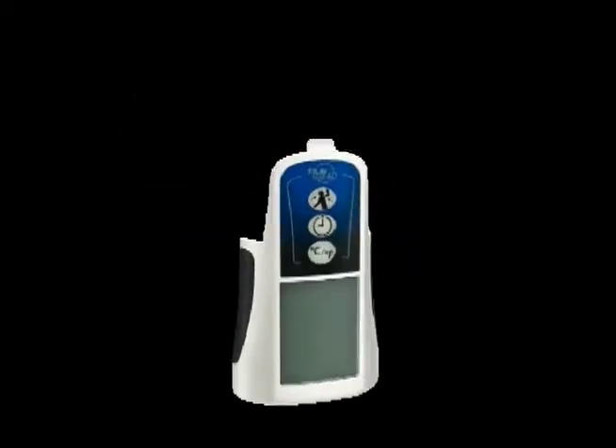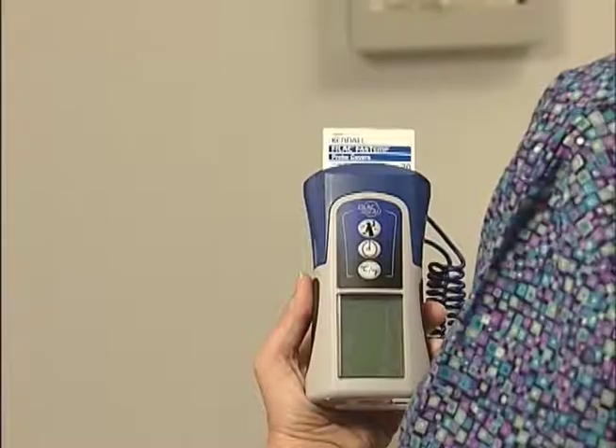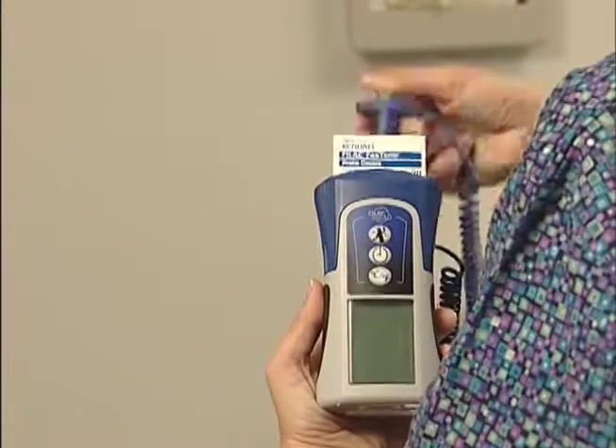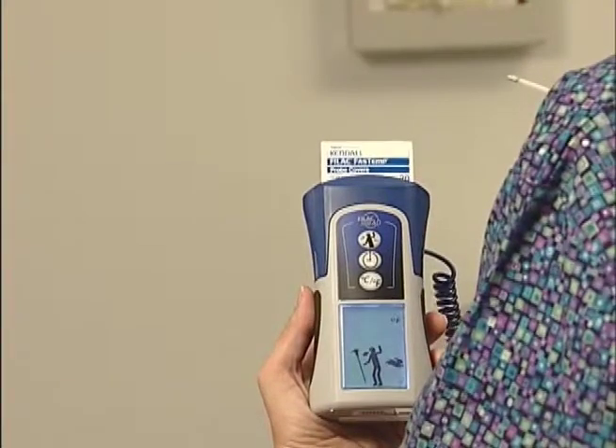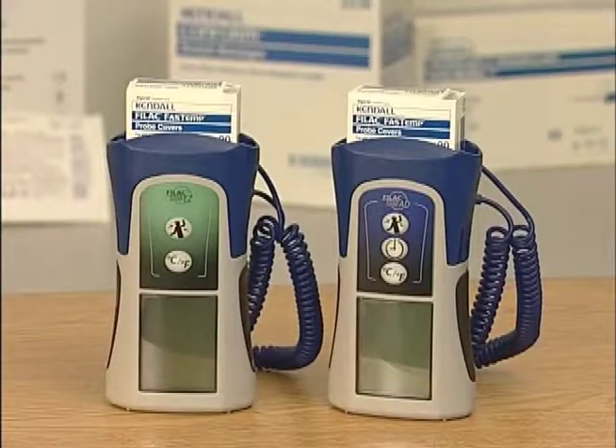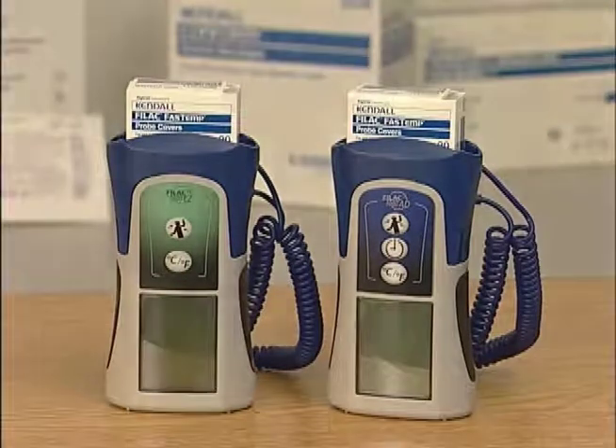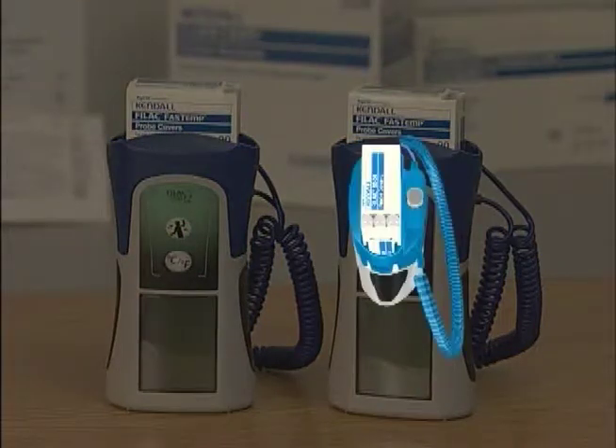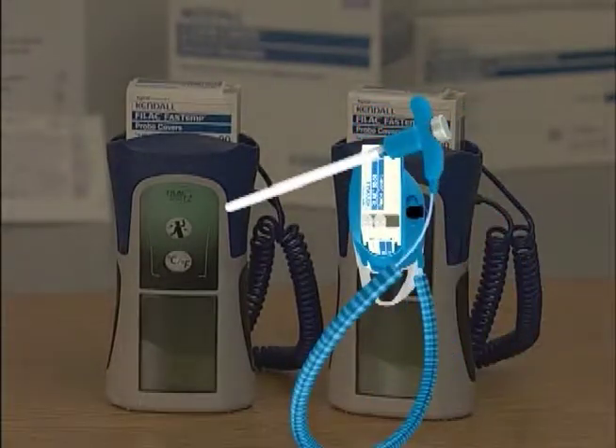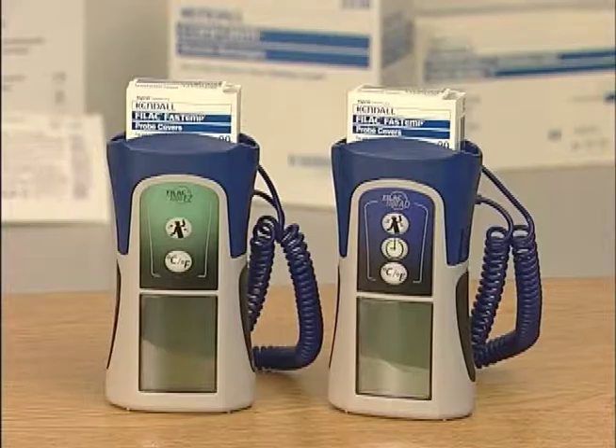When taking a patient's temperature, begin by ensuring the isolation chamber is attached. Remove the probe from the isolation chamber. This will automatically turn on the Filac Advanced Thermometer. Probe covers are conveniently stored on top of the thermometer. A new box contains 20 probe covers. Insert the probe into a probe cover. Push the handle of the probe down firmly until you feel the probe cover snap into place.